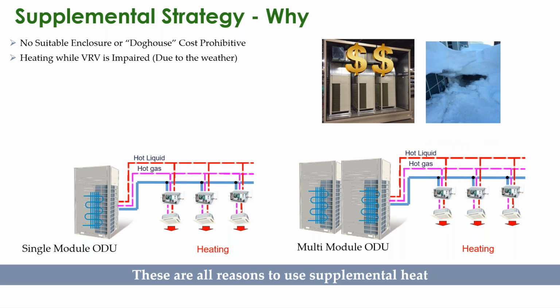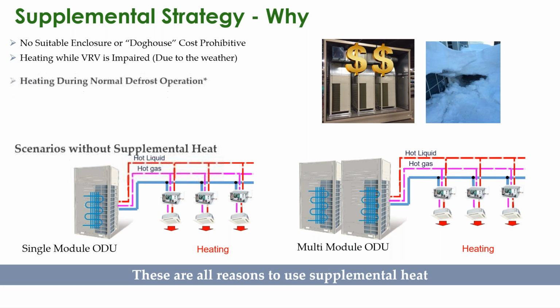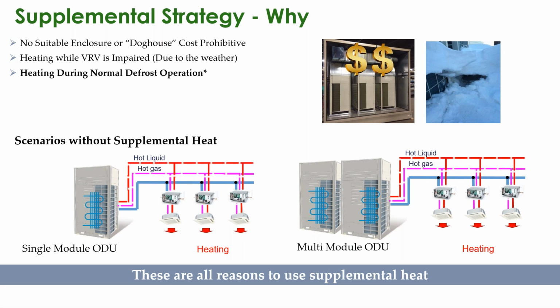Got heating while the VRV is impaired. Snow fell on it, damaged the outdoor unit, you had a catastrophic failure, whatever it may be, you're still getting a little heat, and it's not life-threatening to the occupants. You have some heating during normal defrost operation or catch up after a normal defrost operation, which most manufacturers, the default for defrost is that when you're in a single module, or in some manufacturers' case, multi-modules, the default logic is to switch off all the indoor units, switch the outdoor unit into full defrost, and try to get that defrost cycle over with as quickly as possible, and then get back to heating. Many manufacturers with multi-modules or multi-compressors also offer heating during defrost from the variable refrigerant system, but it is at a reduced capacity.